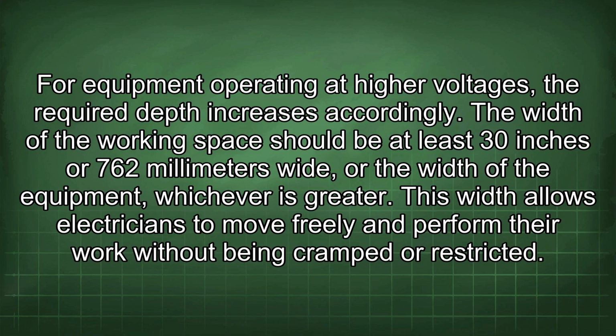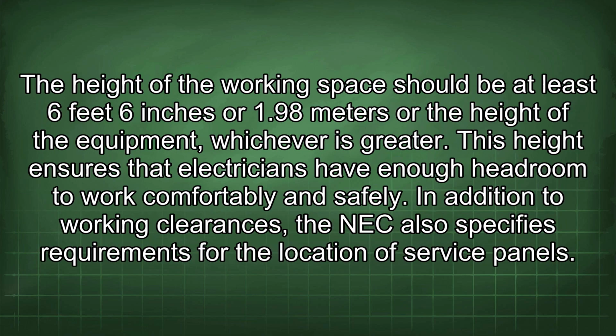The width of the working space should be at least 30 inches or 762 millimeters wide, or the width of the equipment, whichever is greater. This width allows electricians to move freely and perform their work without being cramped or restricted. The height of the working space should be at least 6 feet 6 inches or 1.98 meters, or the height of the equipment, whichever is greater. This height ensures that electricians have enough headroom to work comfortably and safely.